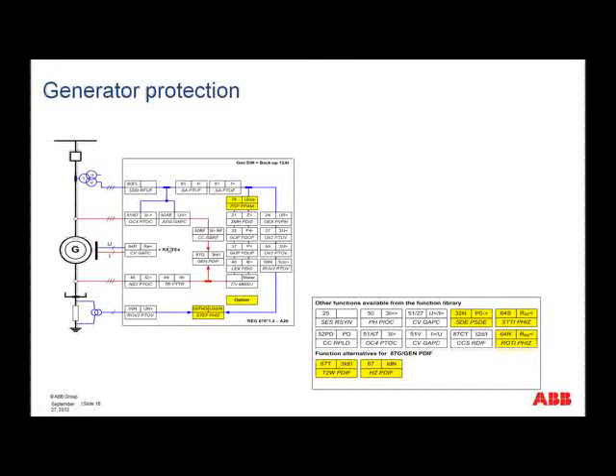Then we have here the rotor earth fault protection, showing the rotor earth fault protection using injection unit. Here we have the 95% stator earth fault protection using voltage based. We are also showing here the 100% stator earth fault protection based on third harmonic.